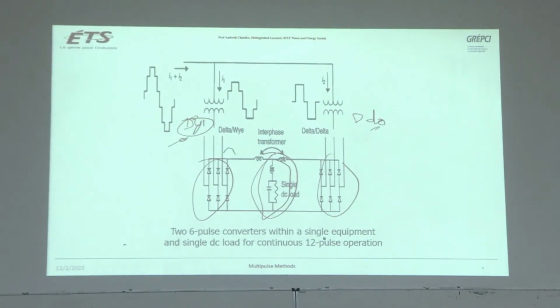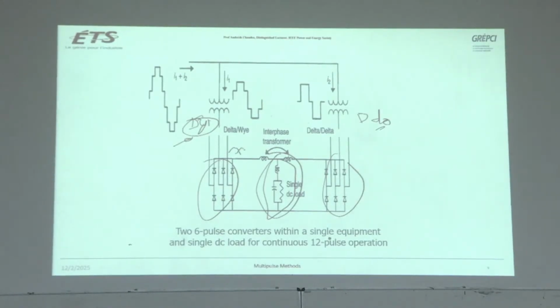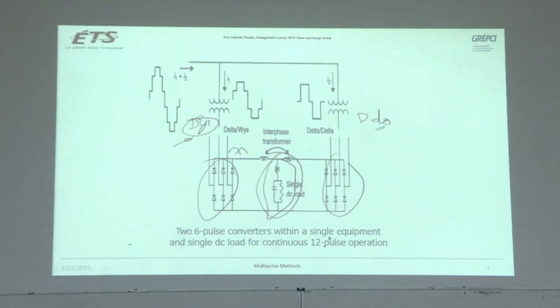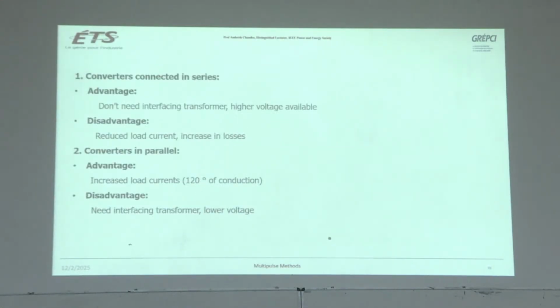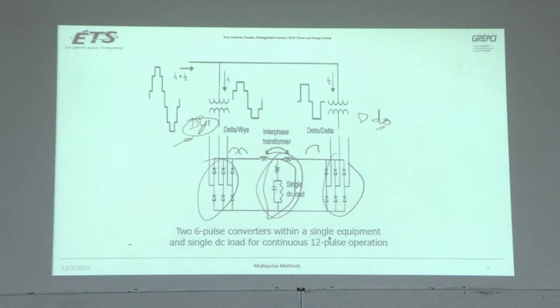So basically the voltages coming here, see, there is a 30-degree phase shift between the two voltages. So the ripples will be generated on this side, which has the instantaneous 30-degree phase shift. So the voltages are not equal, and there may be some circulating current problem. That's why we use an interphasing transformer to smooth out the operation.